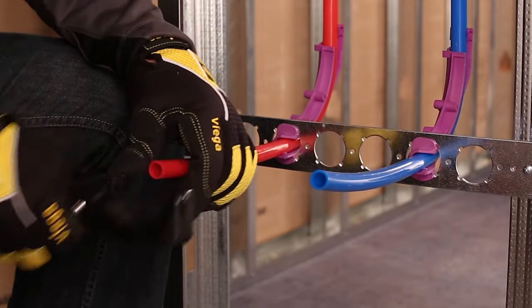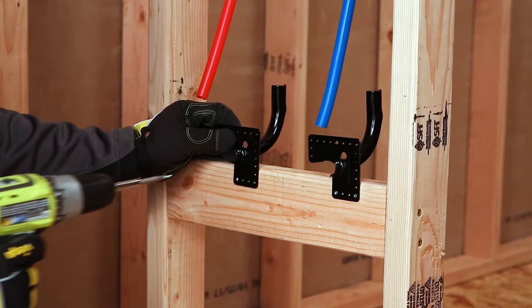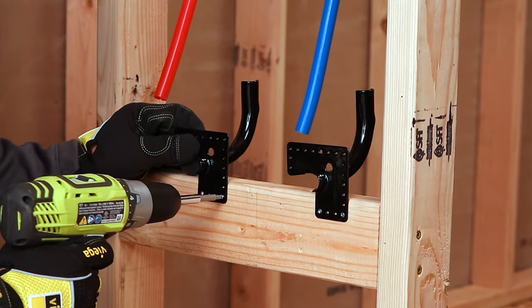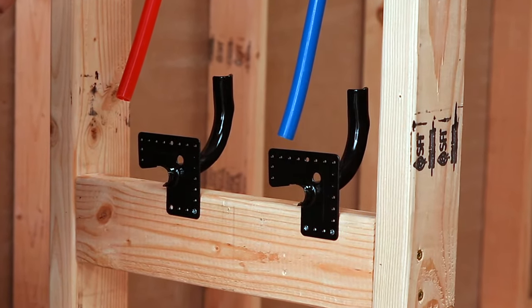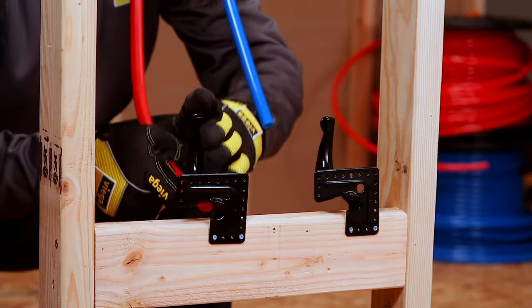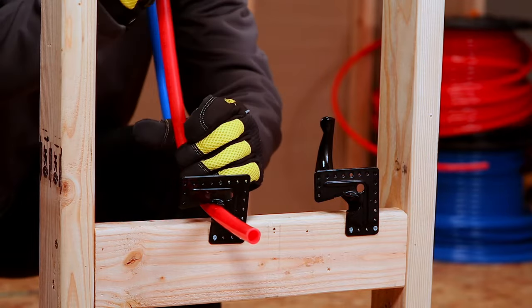Use the following steps when installing Viega stubouts. First, select the desired location to terminate the distribution lines. Using either a horizontal wood 2x4 or Viega stubout bracket, create a support for the PureFlow PEX tubing to stub out. Insert the stubouts or PEX into the bracket and secure via tubing clamp stubout.